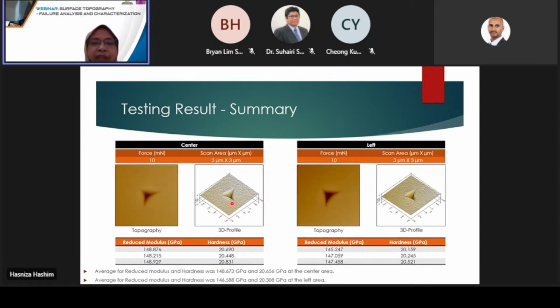Before we do the indentation, we have already scanned the area to be indented. From this in situ image, we can see that the surface is very fine and smooth, and this meets the requirement for nano indentation. Once we do the nano indentation, we can capture the image using in situ imaging, where we can see the topography of the indentation and also the 3D profile. It comes out with the result of modulus and hardness. From these samples, we can see that both the center and left area of the wafer produce almost the same result.